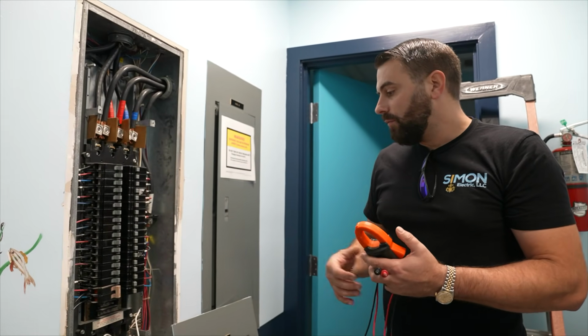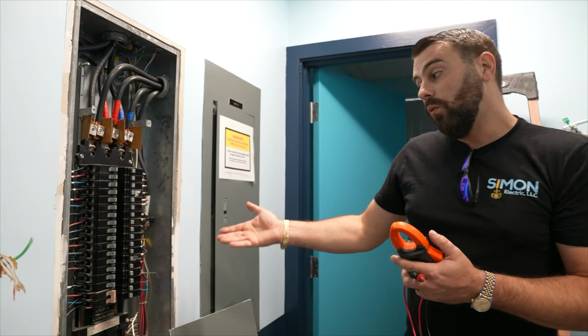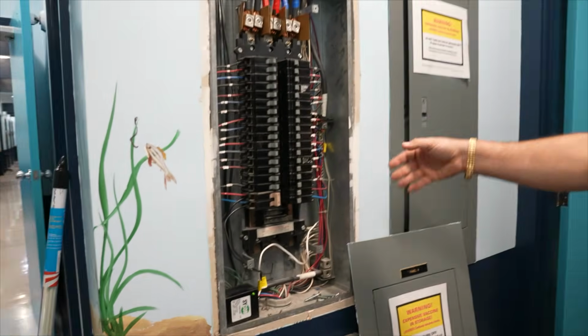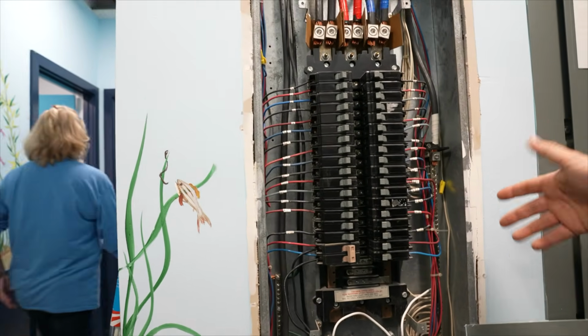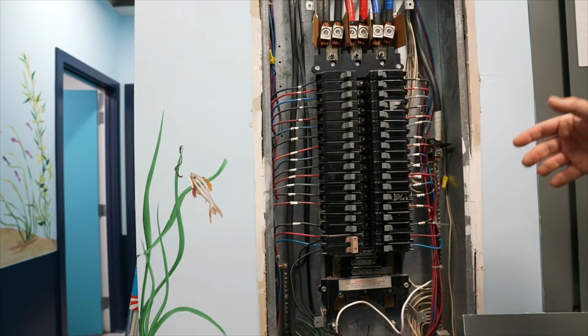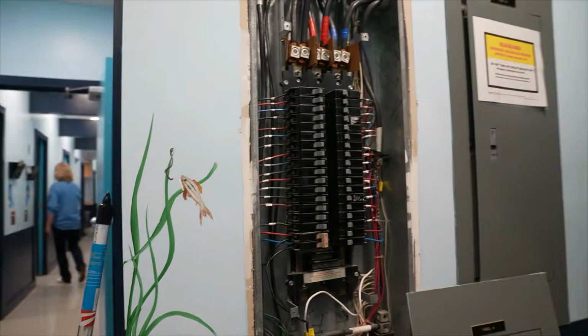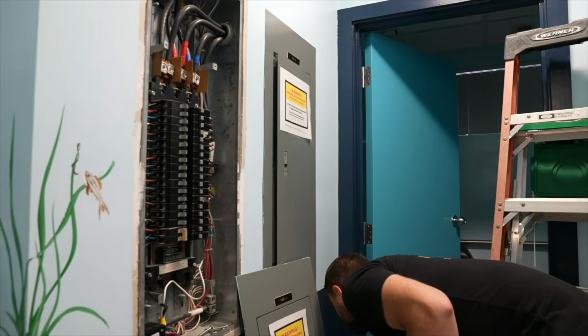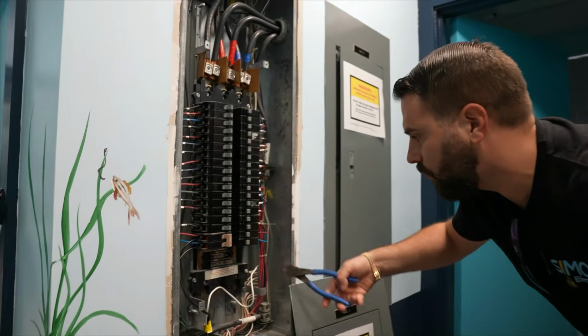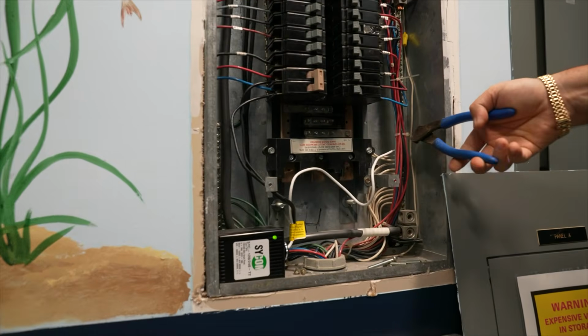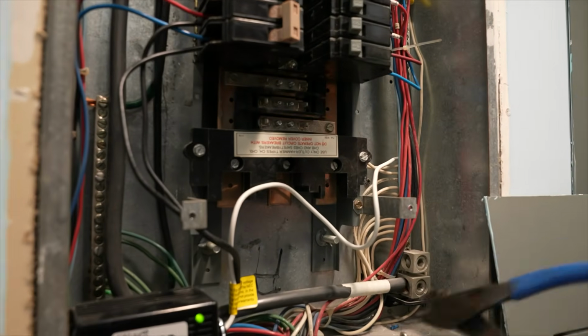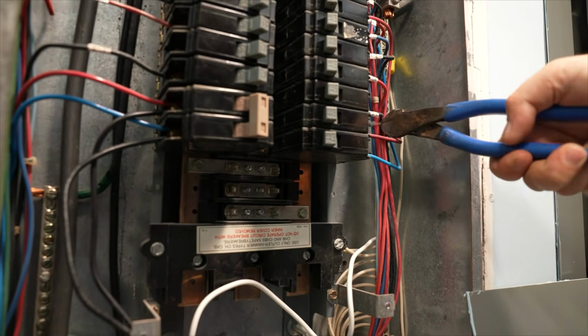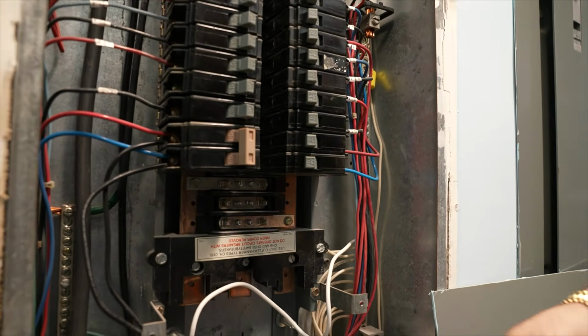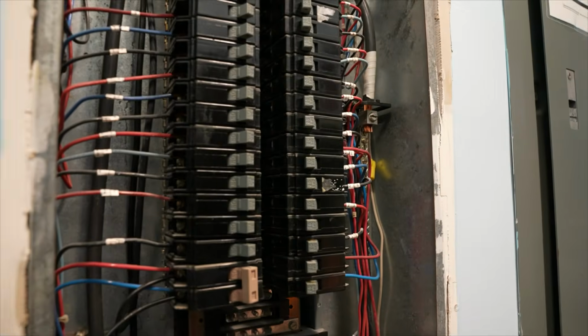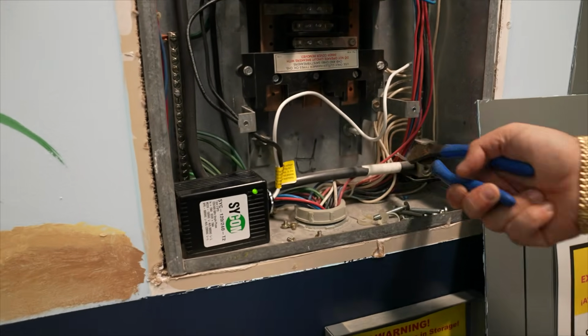Now, one thing you can do when you install the panel initially is bundle the hots like that, but make sure you cut them, because if I cut these right now, you'll see the wires stay where they're put - see, it ain't going nowhere. So you can do that in the beginning as well. We'll cut all the bundle ties off to make sure there's never an issue with that.